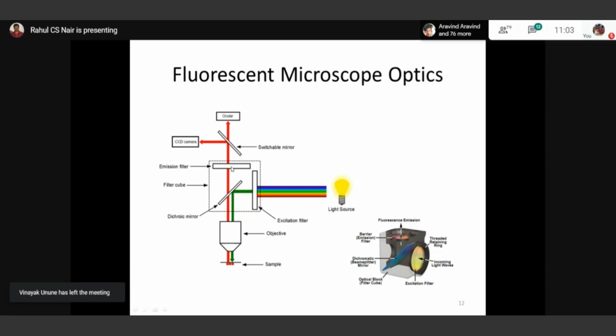Like the earlier light microscope, all these optics are fixed onto a suitable frame. So this is the frame, and we have the light source here, this small dark colored part. You can see the light coming through this and various optics. It is guided by various optics, and then the dichroic mirrors are equipped here, and it falls to the sample, through your suitable objective, which you can twist to the correct direction.